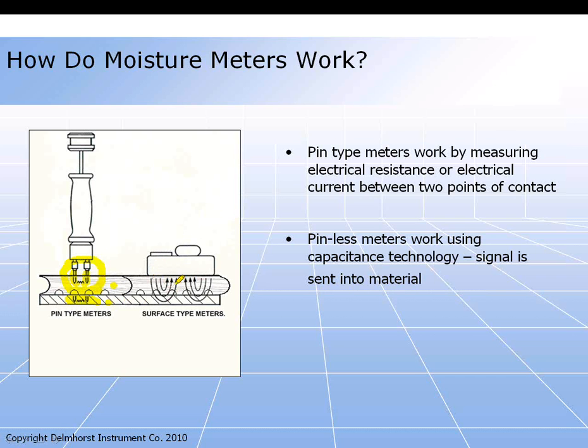With a non-invasive meter, the depth of penetration is typically between about half an inch and three-quarters of an inch. We'll talk about some limitations there, but the main difference in terms of information is you won't necessarily be able to get down through a floor to a subfloor, or through drywall into insulation, because there's a limit to the signal being sent out.